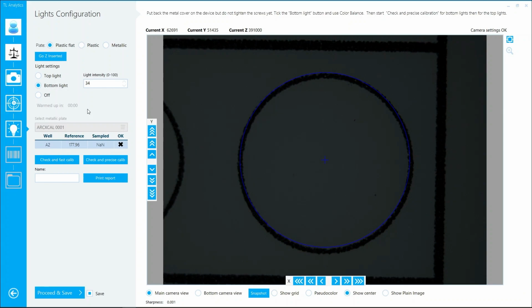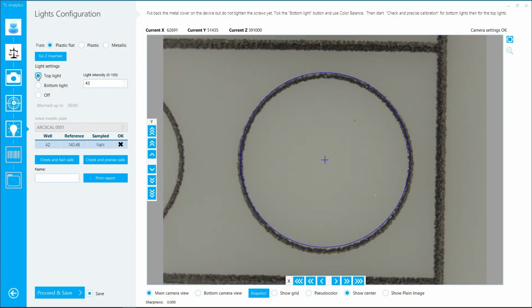It is either bottom light or top light. Each of these are calibrated with a different plate. Opaque plate, the white one, is for the top light, and the transparent plate is for bottom light. So after you select correct light according to plate inserted, in my case it's top light, fill in your name and press check and fast calibration.